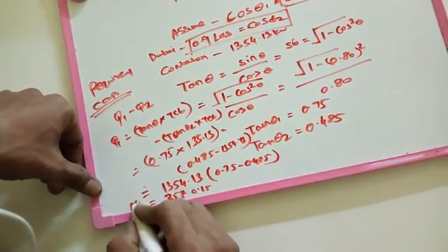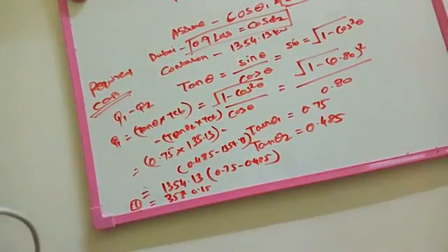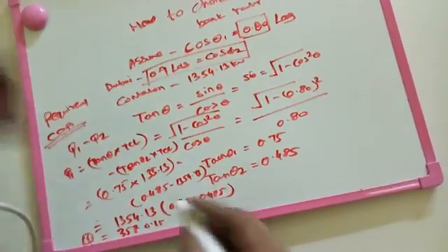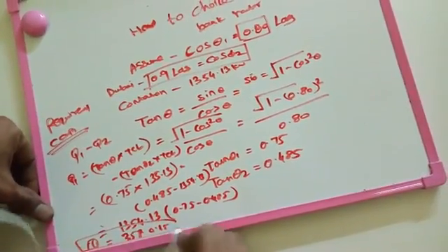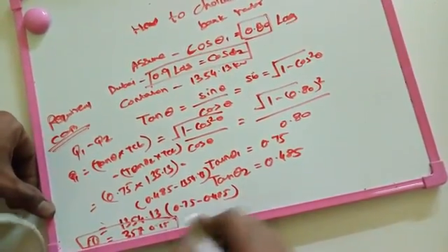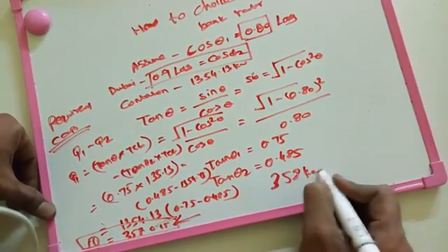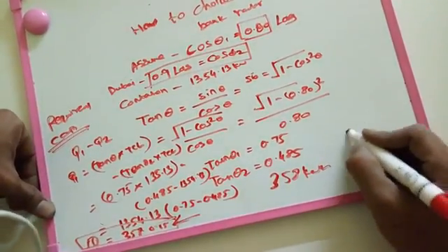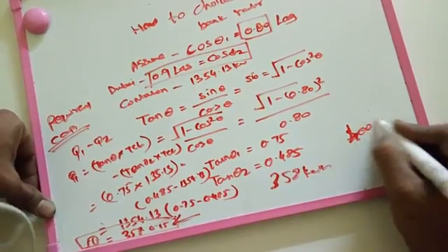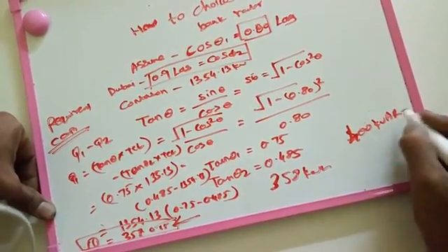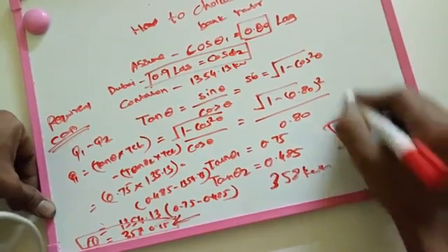This is the rated capacity. This is the final answer for what capacitor we need, how much capacitor we need. Here we got 358 kVAR, so we choose 400 kVAR for capacitor bank for this assumption.